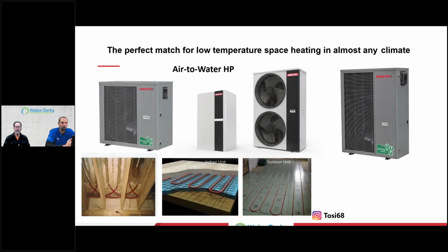Remember, if my concern is only maintaining temperature in that tank, as far as what's going to cost me energy, the majority is running that condenser, the heat pump. So if I have more storage, I can keep drawing down that tank and still satisfy the space, so that when I do turn on that source, whatever it may be, it could be a boiler, it could be a heat pump, it could be a majority of things, the tank is being asked to work.